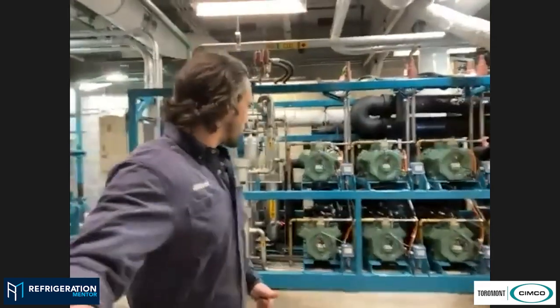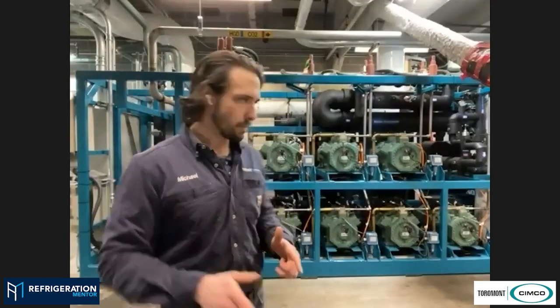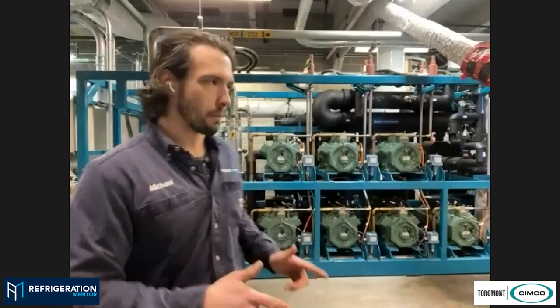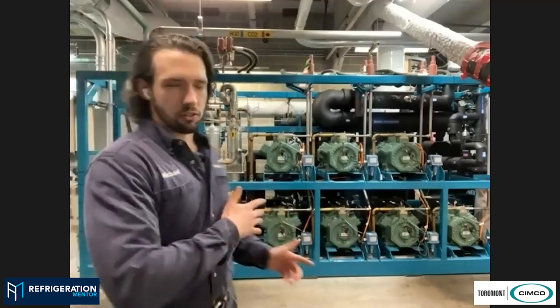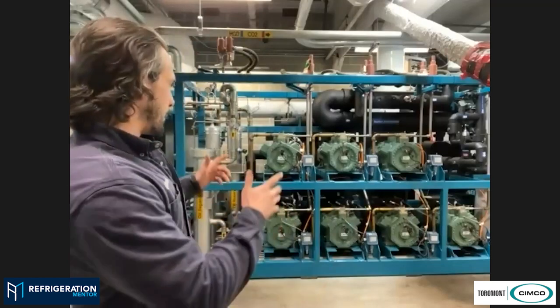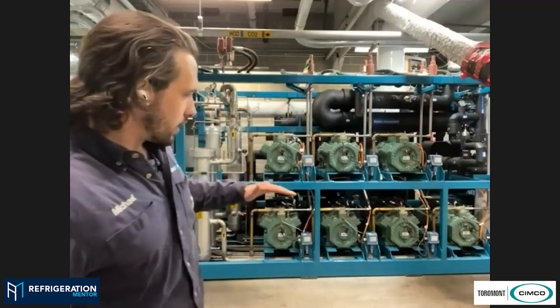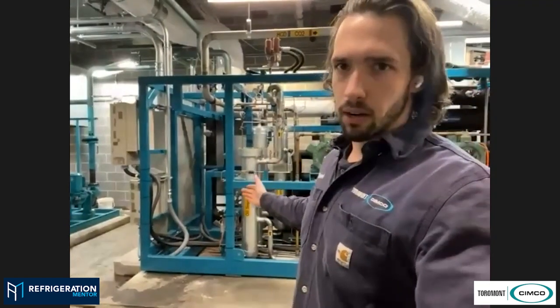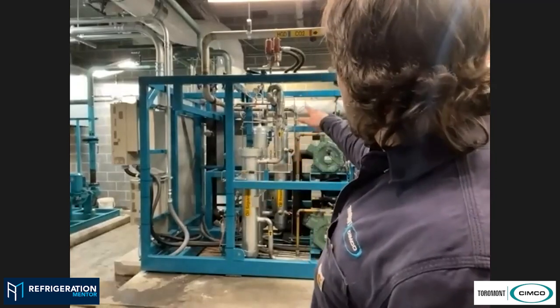Okay, so starting over here, this system has 7 Bitzer 6-cylinder reciprocating compressors, and compressor number 1 runs on a VFD. The remaining compressors are across-the-line start. Compressor number 1 will always start first on the VFD, followed by a rotation of the additional 6 compressors based on runtime. The top rack and lower rack are shared on a common suction group. There's not a medium or 2-stage setup on this site. However, the top rack and lower rack each have their own discharge header and Temprite oil separator. There are actually 2 separators as opposed to 1. The outlet of the oil separators come to 2 check valves, where the discharge then becomes common for the system.